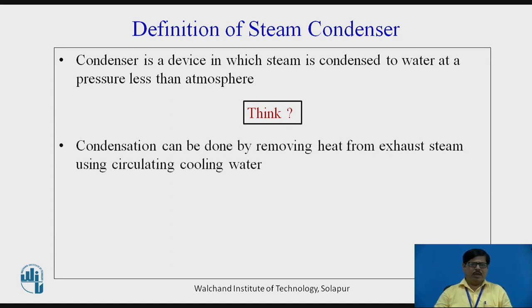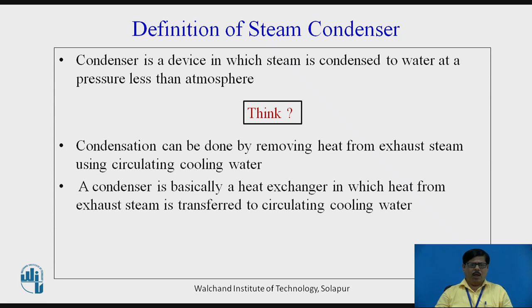Condensation can be done by removing the latent heat of evaporation from the exhaust steam coming out of the turbine or steam engine using circulating cooling water. After removing the heat, the exhaust steam gets converted into saturated liquid. A condenser is basically a heat exchanger in which the heat of steam is given to the circulating cooling water, and steam gets condensed from vapour state to liquid state, whereas the cooling water gets heated because it receives the heat from exhaust steam.